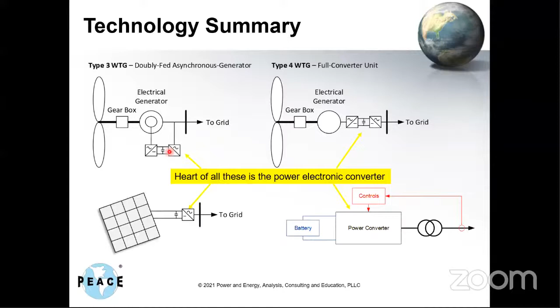So at the heart of all these technologies is this power converter, and that's really what drives the dynamics, if you will, of these devices. Whereas in the old world, we've been used to synchronous machines, which behave completely differently, of course. And so this is a kind of simple diagram to try to illustrate that difference. So in the case of a synchronous machine, we have a rotating magnetic field on the rotor of the machine, and we have a rotating magnetic field on the stator, which is connected to the grid.